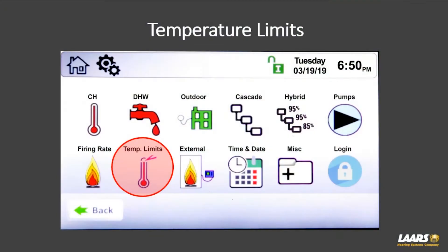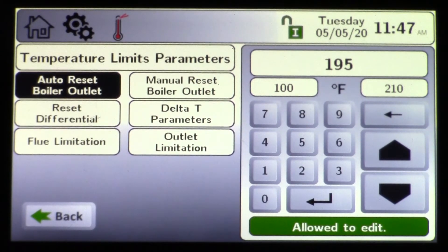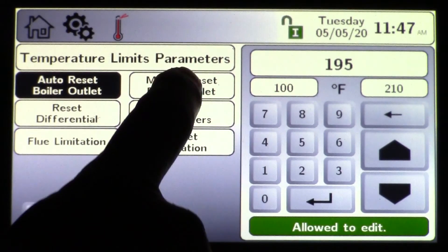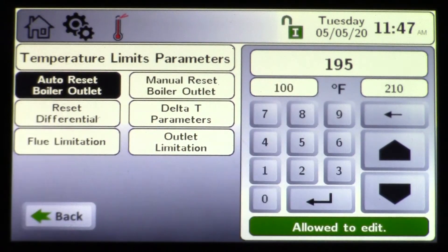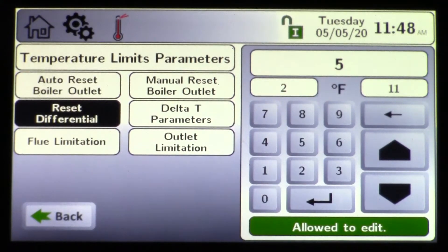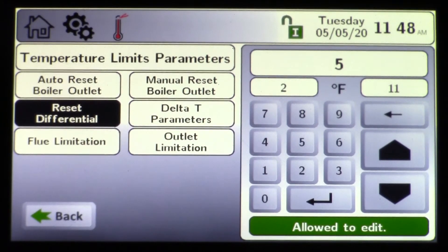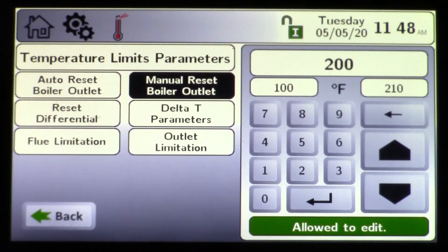Next we'll talk about temperature limits. These are the built-in high limits for a boiler. You have auto reset and manual reset. The auto reset — if the boiler reaches, in this example, 195 degrees, it would shut the boiler down. However, it would reset based on its delta T, or differential. An example is five degrees, so at 190 degrees it would allow it to refire.